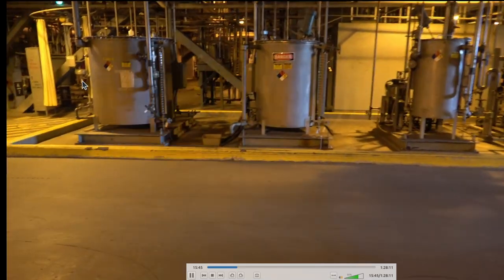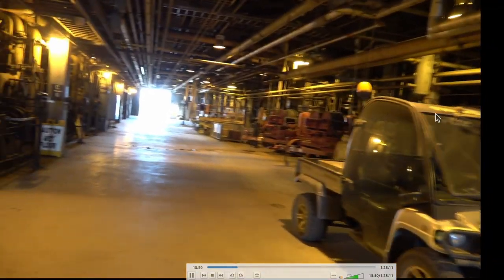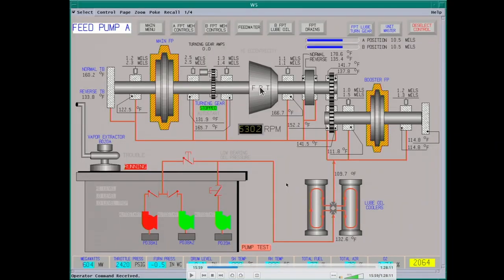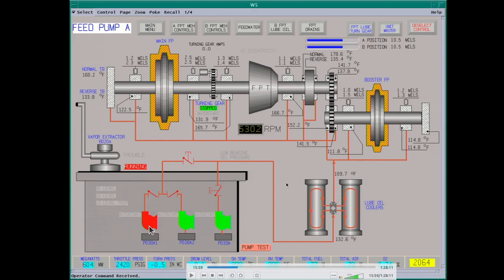Here's the feed pump floor. Here's your feed pump turbine — it goes through a gear reducer to your booster feed pump. This runs at 3,600 RPM. Over here we have the main feed pump. It has a turning gear on it — you can monitor your vibrations and bearing temperatures. It has a lube oil cooler — same setup as the main turbine. You have your AC oil pump, a backup AC pump, and a DC pump that will run if you lose all power to bring the plant down.